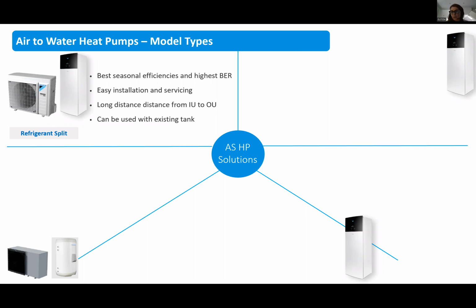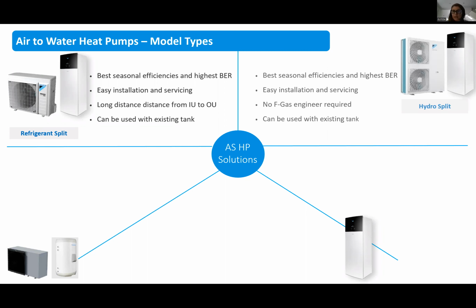With refrigerant splits, you have no concerns about freezing, and you have no concerns about heat loss in the pipework between the indoor and the outdoor unit. The next one then is a hydro split. The hydro split, similar to the refrigerant split, but it's a water connection between the indoor and the outdoor unit. And when you have a water connection, you generally want to keep your units a lot closer together. You're reducing heat loss, and your pipework needs to be very well insulated to make sure that you don't have freezing in very low temperatures.